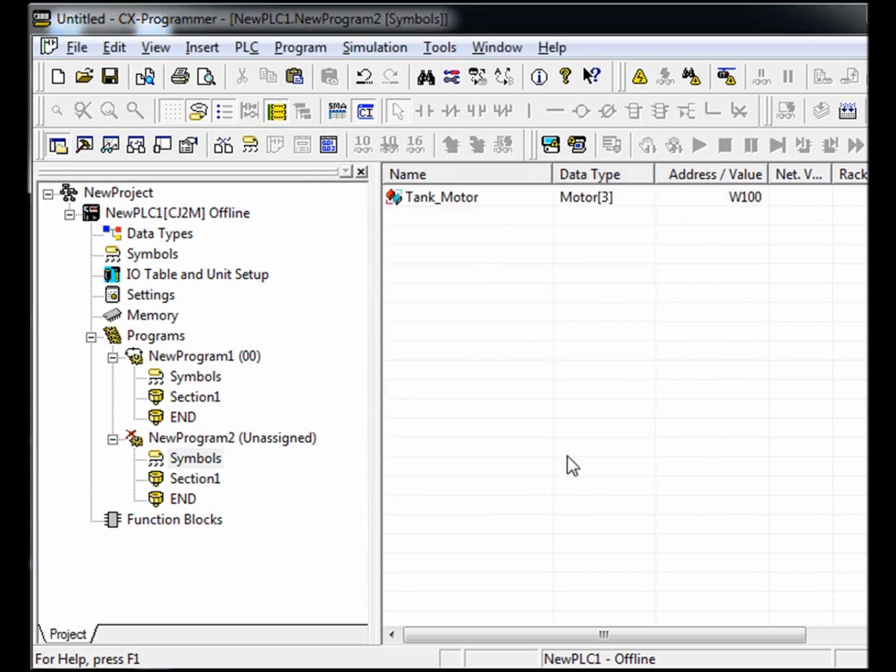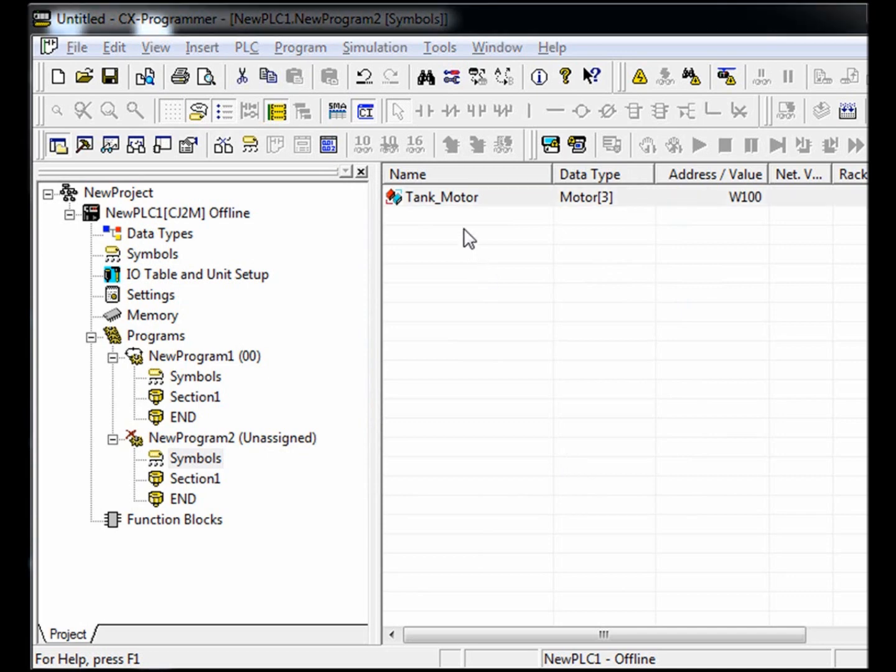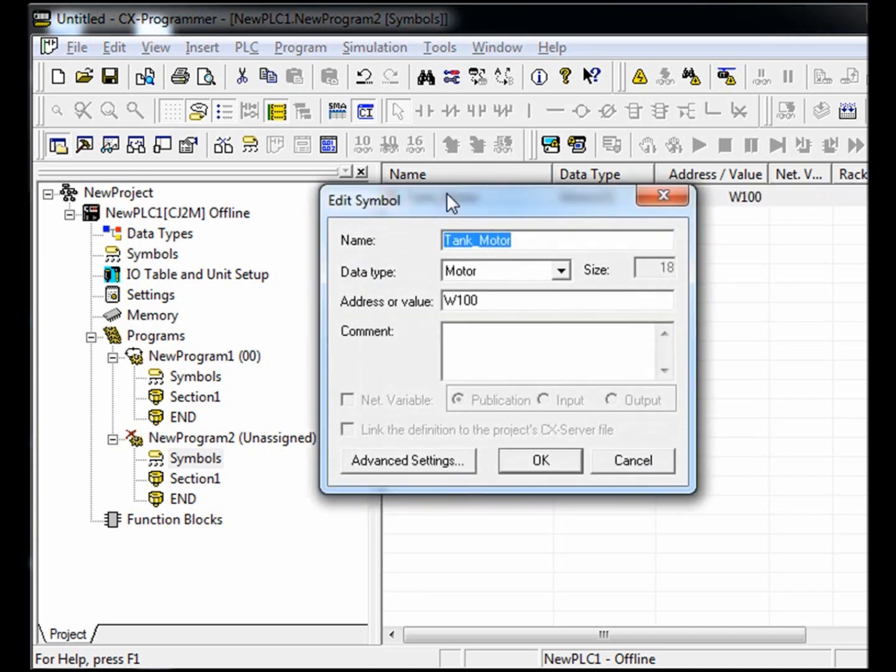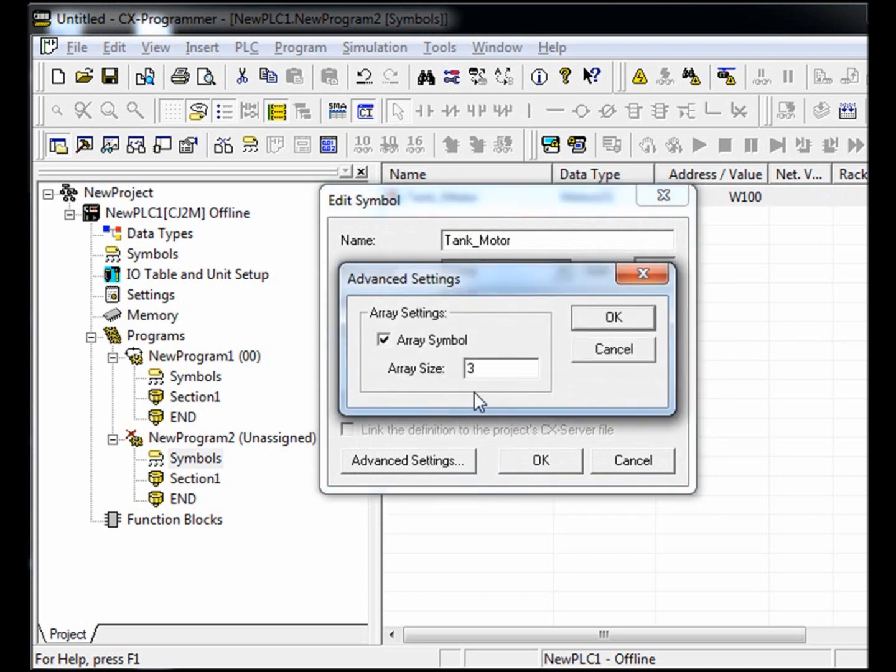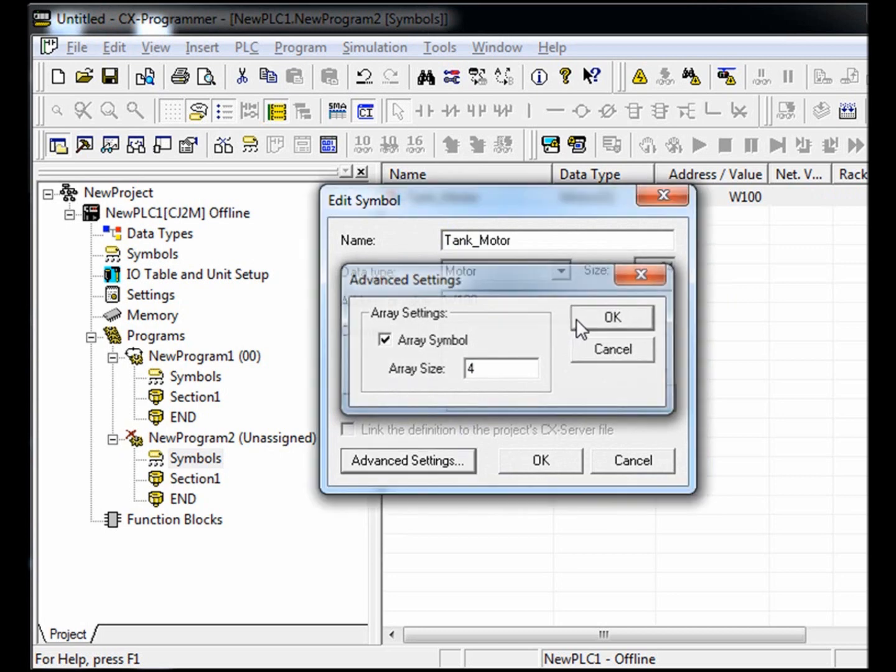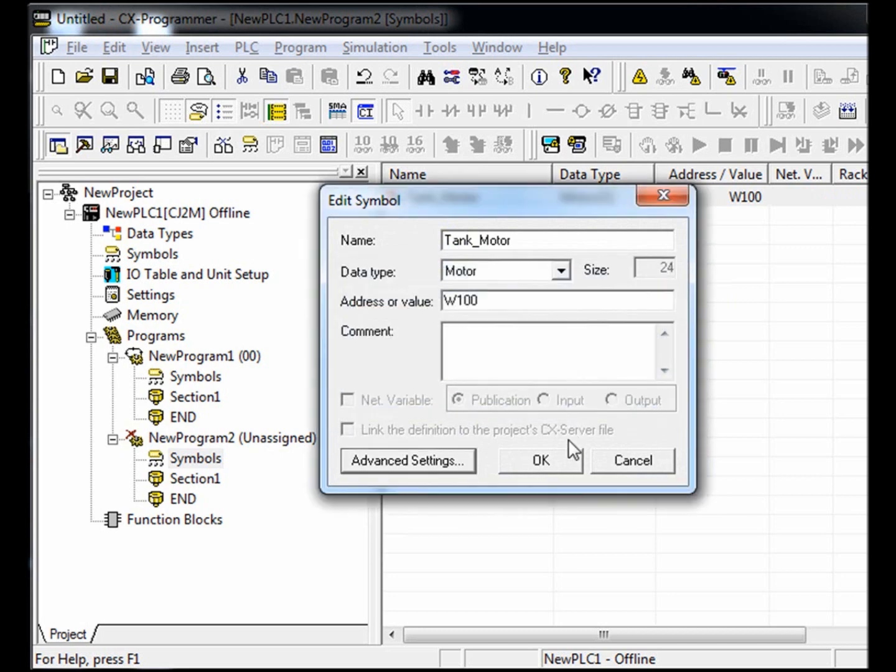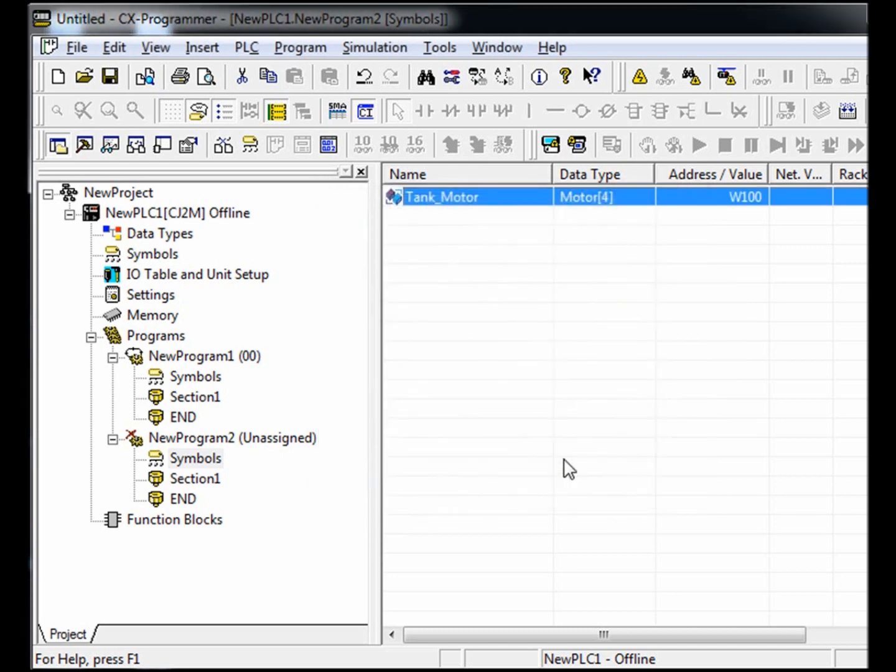In the future, if we ever need to add a motor to our system, all we need to do is increase the motor array count, which is very simple. By double clicking the symbol name tank motor, selecting advanced settings, and inserting four in the array size, we now have a fourth motor that includes all of the attributes of the original three.